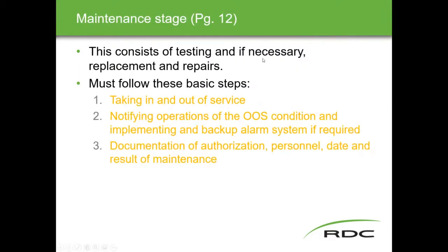The maintenance stage consists of testing and, if necessary, replacement and repairs. Basic steps include: taking the device in and out of service, notifying operations of the out-of-service condition, implementing a backup alarm system if required, and documenting the authorization — the permit pulled from operations, which contains who did the work, when, what was done, and the success level. This is where control technicians mostly come in.